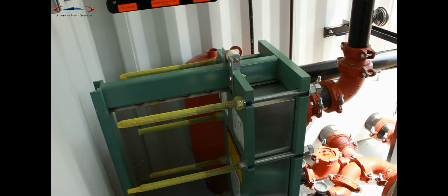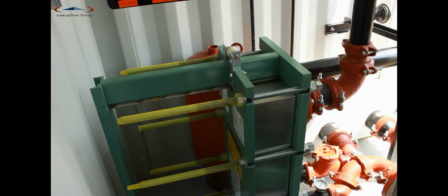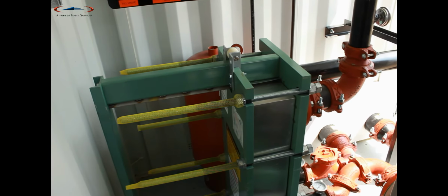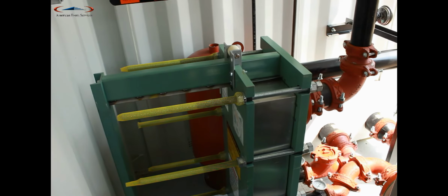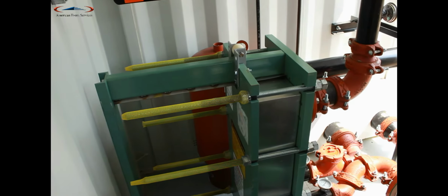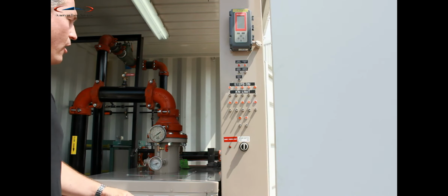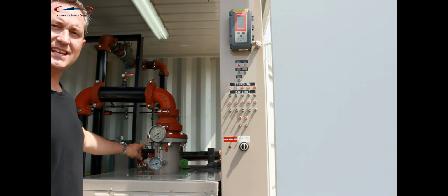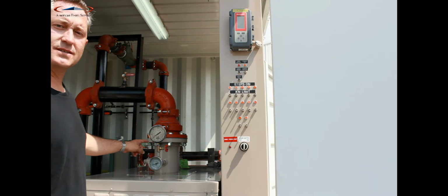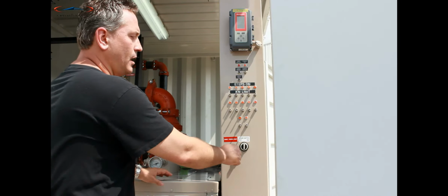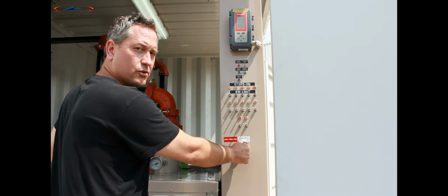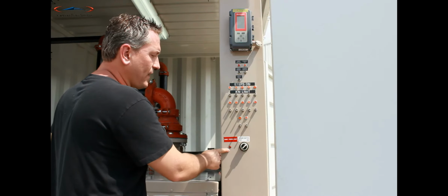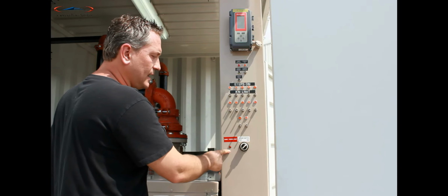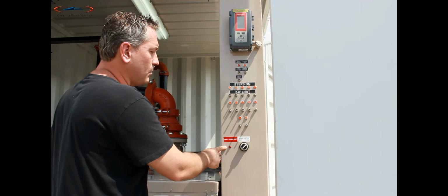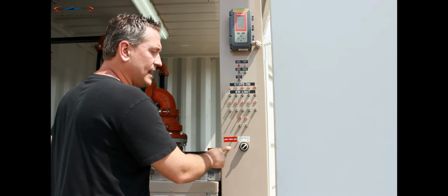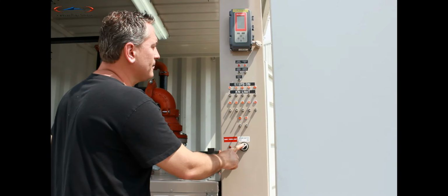The heat exchanger is easily accessible, so the pressure plate can be slid to the back position and the plates inside can easily be removed for cleaning. Once the main breaker is turned on, you need to make certain that you have at least 10 psi in the boiler loop system. Then switch the pump to on. This is your internal pump on the boiler. Check your phase voltage fault right here. If that light's lit, then you either have a phase or a voltage problem. Once that light is off, everything is okay, your pump will be running.